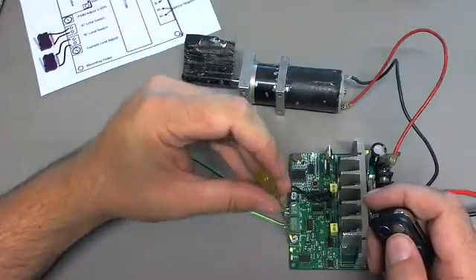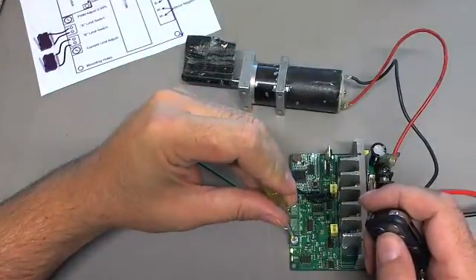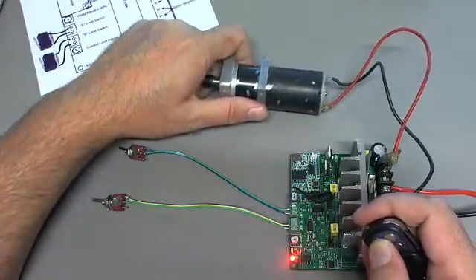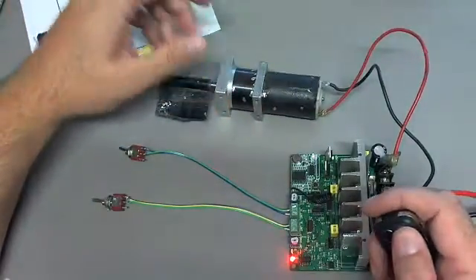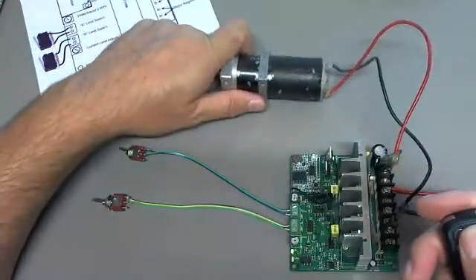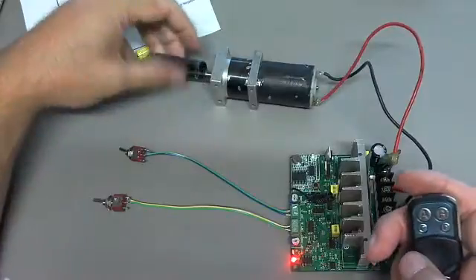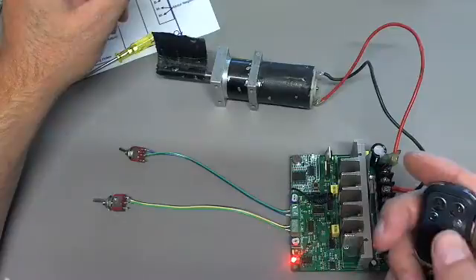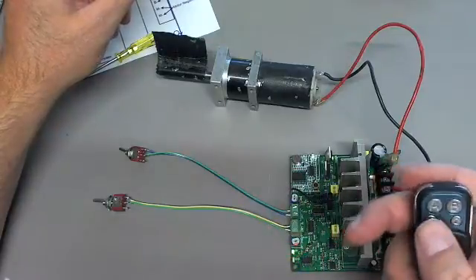If we want to make the current limit more sensitive, we can do that. It's just a matter of adjusting it until it sets it off. See, that way we need to press D to reset it and we're ready to go again. Now we've got it in the forward reverse direction where if the motor stalls it will trigger the fault condition. So again, press D to reset it.